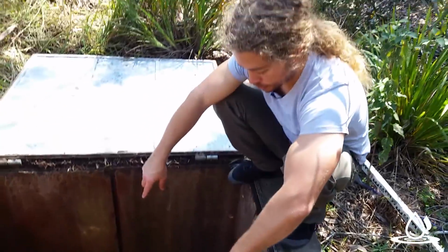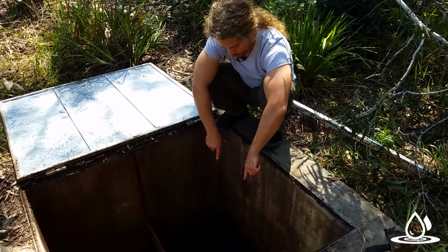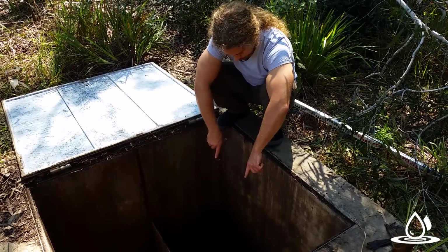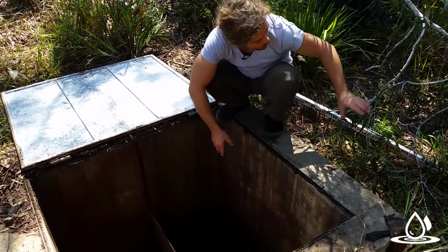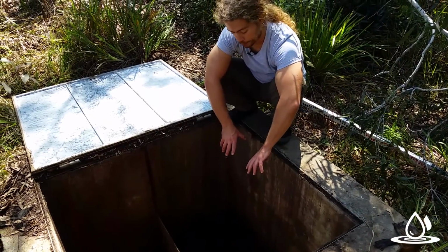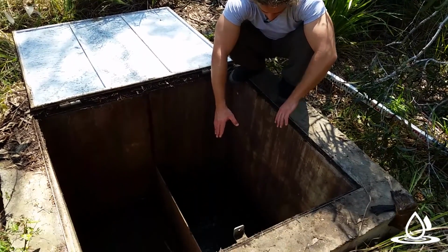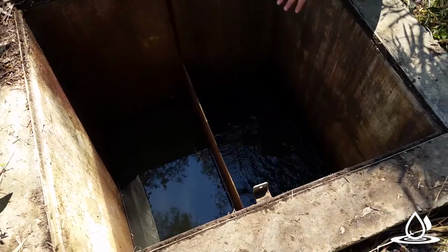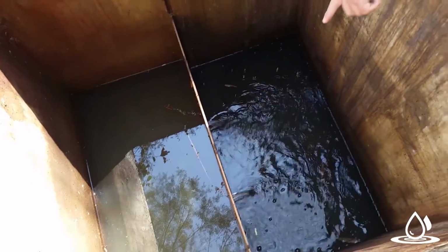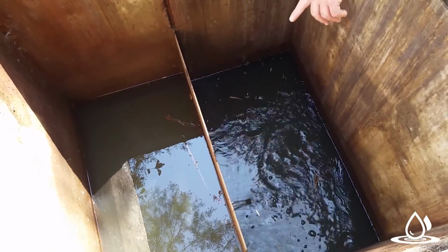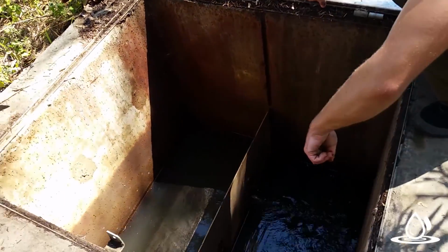The next thing to then think about is what's happening with the water on the downstream level of the pit here. Ideally, this side of the pit, which is the downstream end, will be quite free draining, so that once the water gets through the weir plate, it gets away easily on this side. And in an ideal world, there might even be some sort of sluice valve that you can open to completely drain the wetland out. In this case though, you probably can't see it on the video, but we mentioned the four holes on each side. The bottom hole is actually submerged on this side here.